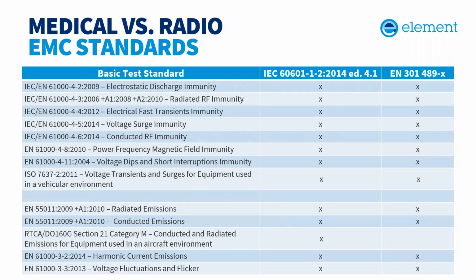When you're integrating a radio for the EU, the EU's Radio Equipment Directive requires immunity testing, which should also be included in the test plan. So -1-2 and 31489 reference the same basic methods as shown here. You can see that they're almost identical in terms of what they're referencing. But the modes of operation and acceptance criteria are based on the risk management aspects. So 31489 is looking for simple radio functionality, while -1-2 is, again, looking at essential performance and basic safety. These are different things, and they shouldn't be confused.